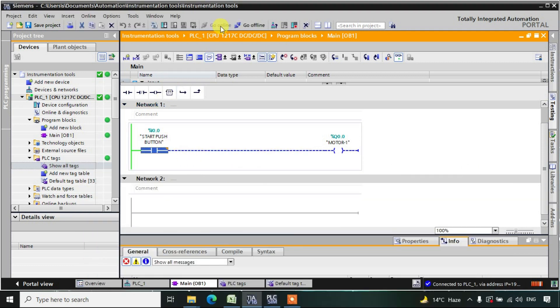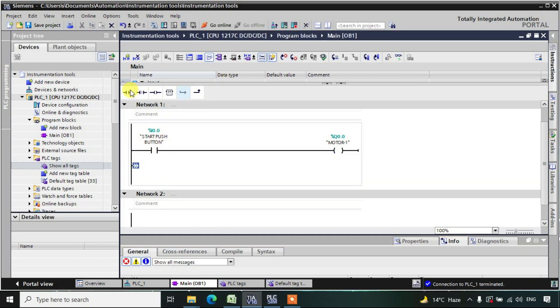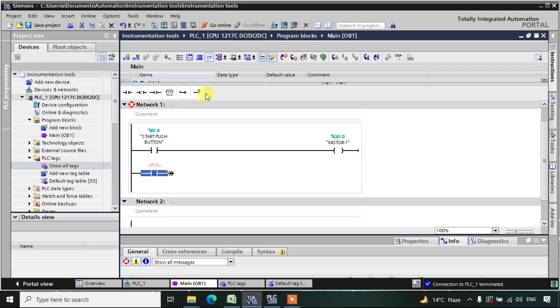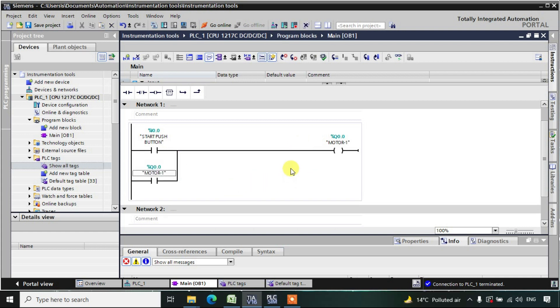We will use the concept of holding. I will go offline and add a parallel branch with an NO contact, then close the branch. I will give this NO contact the address of the output: Q0.0. So the output will be held now.